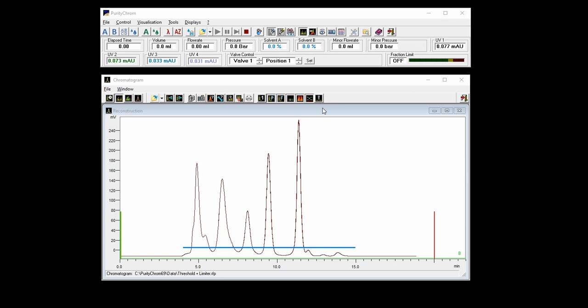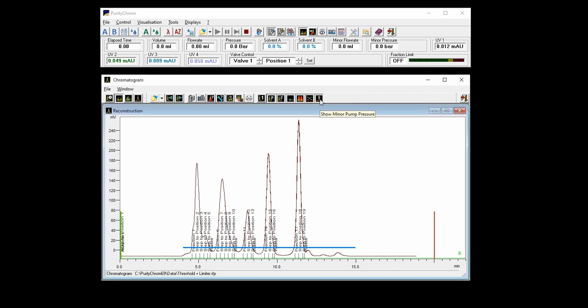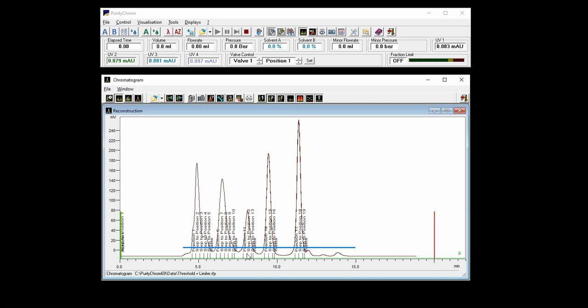Meaning that everything applies that I was telling you before for the limiter fractionation option, just that it is combined with a threshold. And it would look like this in this case: when you go above this threshold here, you start with a fractionation. And then every 0.25 milliliter, the next tube will be used for collection. And whenever the signal goes below the threshold, then it will go back to waste. Like this, you have small portions of your peak which give you the highest purity.